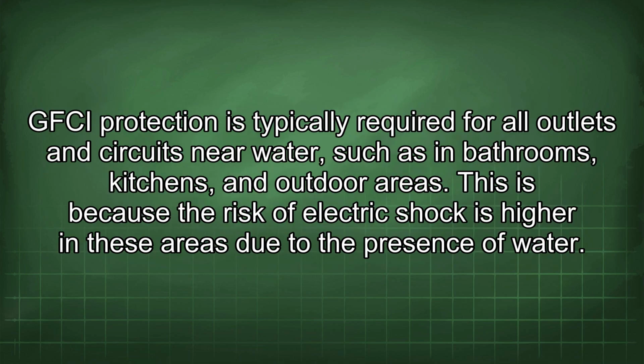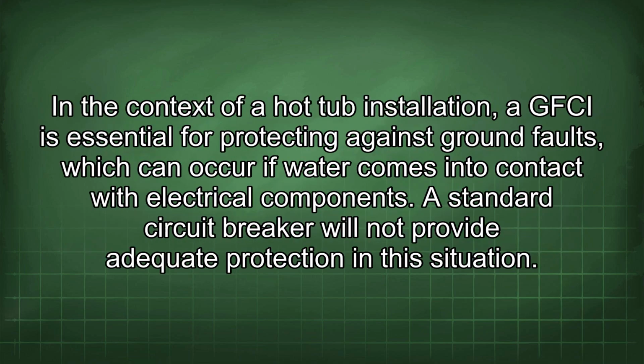GFCI protection is typically required for all outlets and circuits near water, such as in bathrooms, kitchens, and outdoor areas. This is because the risk of electric shock is higher in these areas due to the presence of water. In the context of a hot tub installation, a GFCI is essential for protecting against ground faults, which can occur if water comes into contact with the electrical components. A standard circuit breaker will not provide adequate protection in this situation.